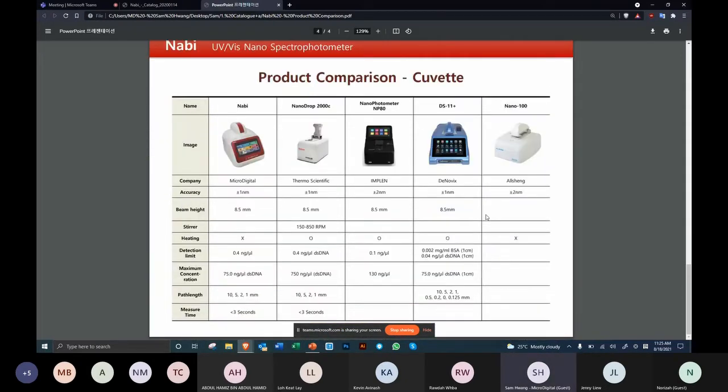For cuvette measurements, accuracy is essentially the same across all competitors. We are in the process of implementing cuvette heating — it will be available very soon. The detection limit is 0.4 ng/µL, which is basically the same for everyone except the NanoPhotometer NP80 which has 0.1. Maximum concentration for ours is approximately 75 ng/µL, and measurement times are comparable across competitors.